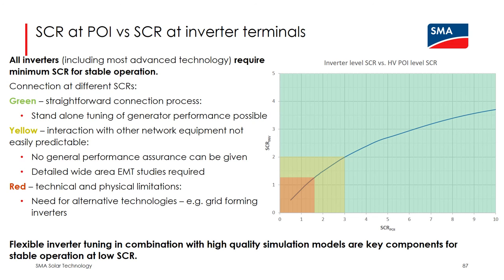And maybe to give you an idea from the SMA experience, what SCRs we see internationally. Projects in Europe typically see an SCR of 6 and up to 20, 30 or even higher, depending on where they're going to be connected. Utility scale projects in the US typically are in a range between an SCR of 2 and maybe 8 or 9. So some low SCR discussions are taking place there as well.